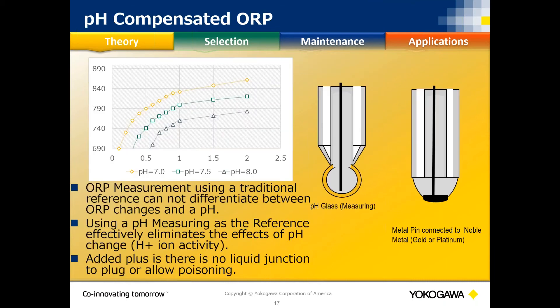Since the ORP electrode is not ion-selective like pH glass — it measures anything in the process — some applications will see millivolt changes because the process pH is also changing at the same time. We need to make sure we compensate for those in applications where this occurs, to correctly interpret what we're seeing.